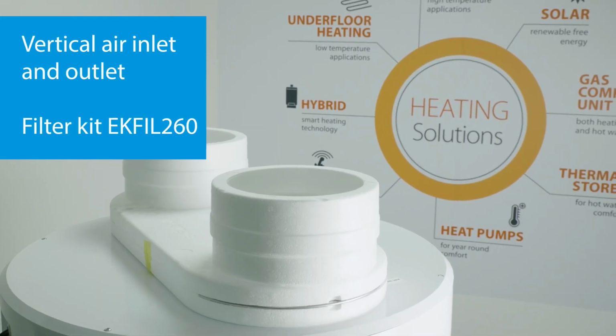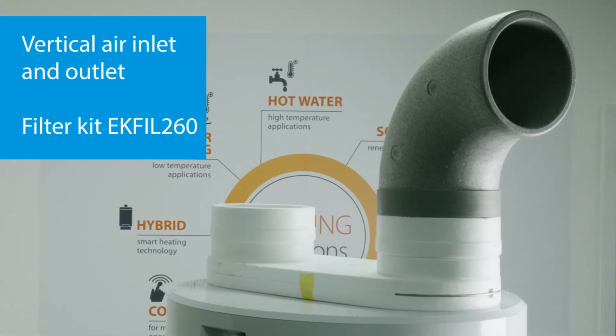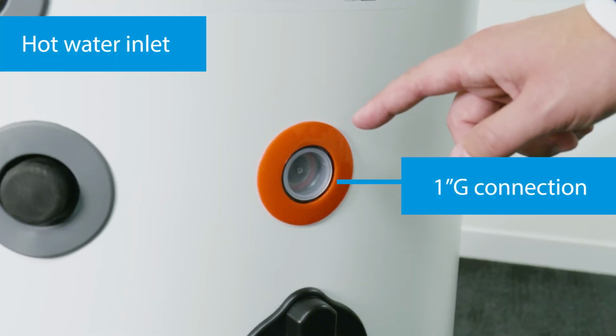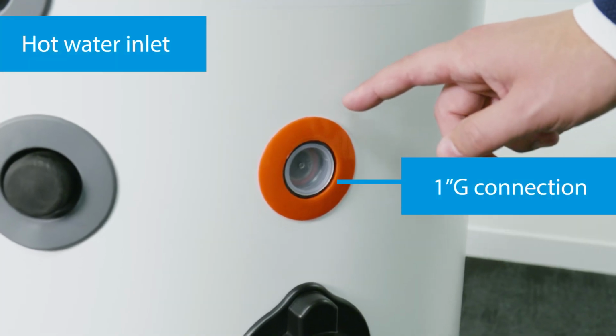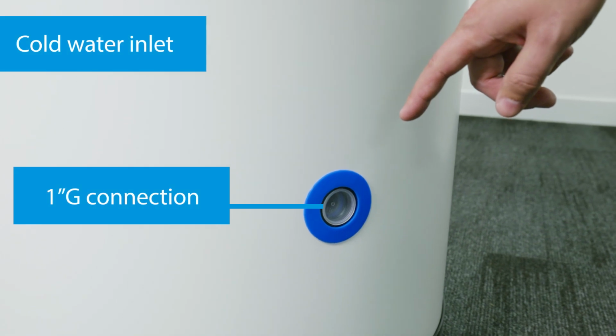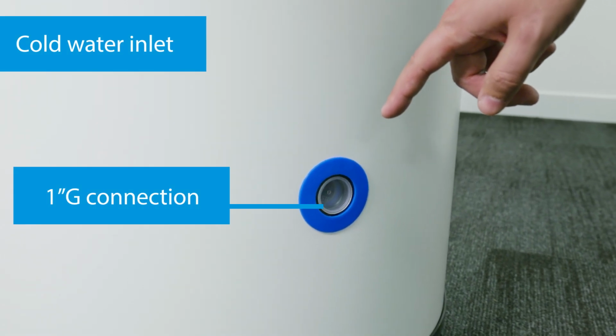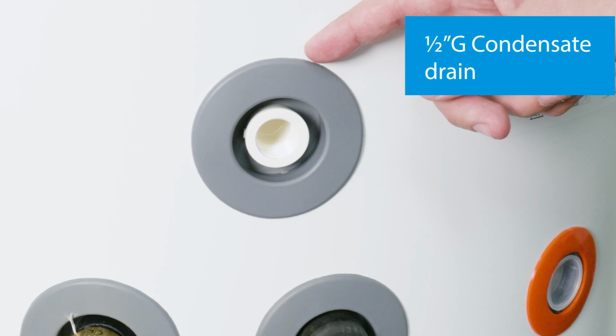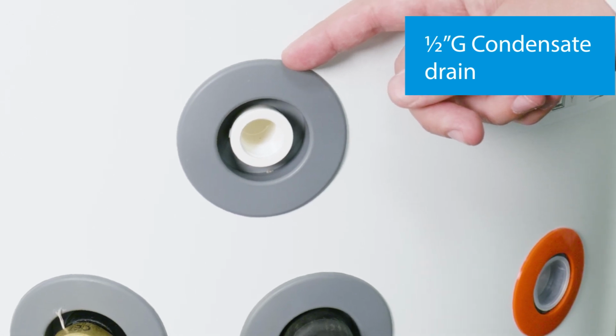The unit itself is separated into the heat pump section at the top and the tank with various connections at the bottom. At the top, there is the vertical air inlet and outlet, and along the body of the tank, the 1-inch hot water inlet is located at the top, the red circle, and the 1-inch cold water inlet at the bottom, marked as the blue circle. The condensate drain is a 1/2 inch size.